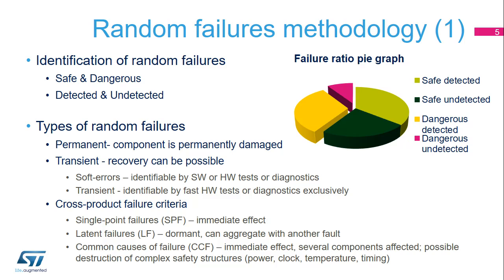Both safe and dangerous errors can either be detected or stay hidden and undetected by the system. The more often dangerous errors are discovered and prevented in time, the more the probability of a failure propagating into a hazardous event decreases. The time needed to detect dangerous errors and prevent hazardous events must fit into the overall process safety time available, which includes all the possible delays and reaction times for the system — for example, on sensors or actuators. For quantification purposes, safety standards recognize a safe failure fraction and diagnostic coverage.